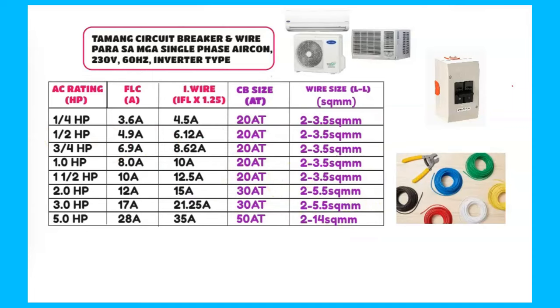And then, based sa table, saka sa data kanina, so we can come up itong selected na size of wire natin. So, again, pag 1/4 HP, dapat meron tayong dalawang 3.5 square mm. So, until siya sa 1.5 HP, ang gamit natin is 3.5 square mm. So, pag 2 to 3 HP, ang gamit dapat na size of wire is dalawang 5.5 square mm. So sa 5 HP, ang gamit dapat is 14 square mm. So malinaw sa PEC na ganun yung wires na dapat gamitin natin.